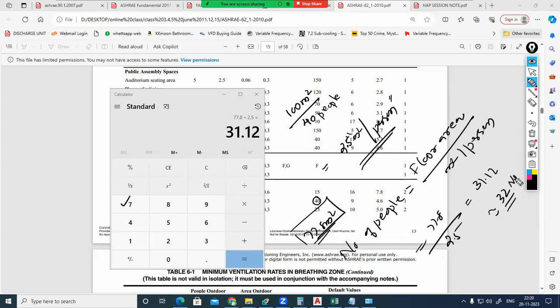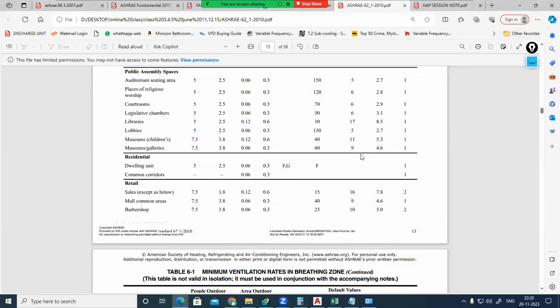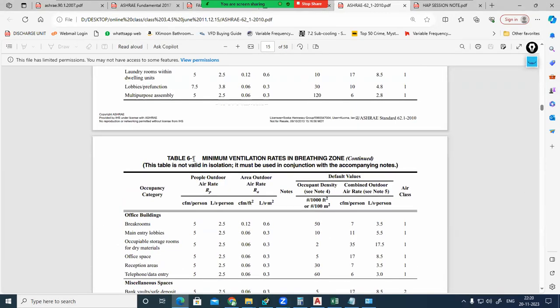Clear now? We are not always going to get the furniture layout. If you are not having the furniture layout, and in exceptional areas like a sales area, a furniture layout is not practically possible. So in those locations, the number of people we can calculate with respect to the occupant density, meter square per person value. From where can we take it? From the same Table 6.1 of ASHRAE 62.1, here we can find occupant density.